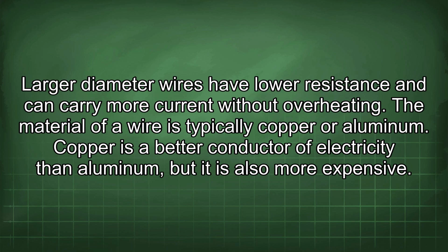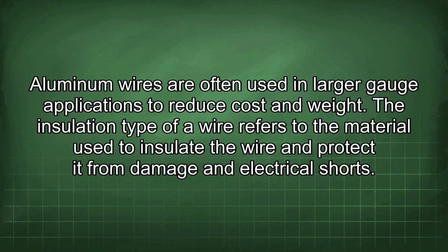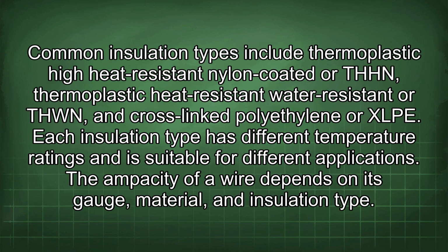The material of a wire is typically copper or aluminum. Copper is a better conductor of electricity than aluminum, but it is also more expensive. Aluminum wires are often used in larger gauge applications to reduce cost and weight. The insulation type of a wire refers to the material used to insulate the wire and protect it from damage and electrical shorts. Common insulation types include thermoplastic high heat-resistant nylon-coated, or THHN, thermoplastic heat-resistant, water-resistant, or THWN, and cross-linked polyethylene, or XLPE. Each insulation type has different temperature ratings and is suitable for different applications.